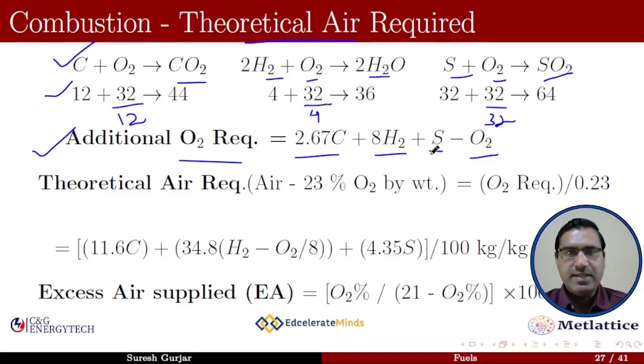Next is theoretical air required. We know that air consists of 23 percent oxygen by weight, so the theoretical air required is the additional oxygen required divided by 0.23, which equals [11.6C + 34.8(H2 - O2/8) + 4.35S] divided by 100 kg of fuel.